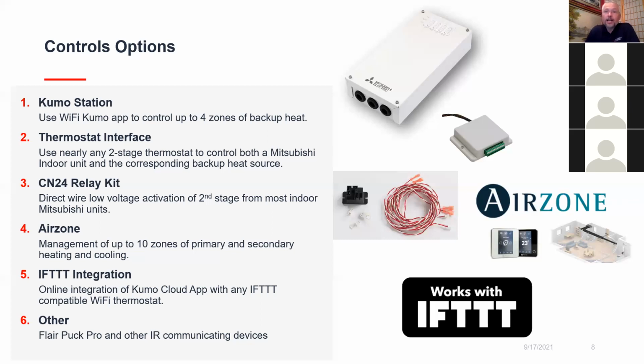If you were to connect a relay kit to it, which is really just a low voltage relay, you could call in the cavalry using that signal and just turn on whatever zone using basically a run of thermostat wires. I'll get into greater detail on that, but that's a very simple, very low cost, and effectively bulletproof method for controlling backup heat to zones.